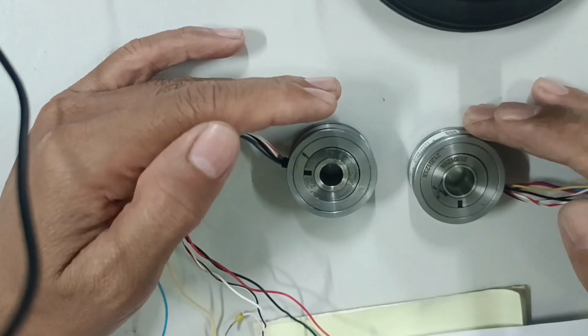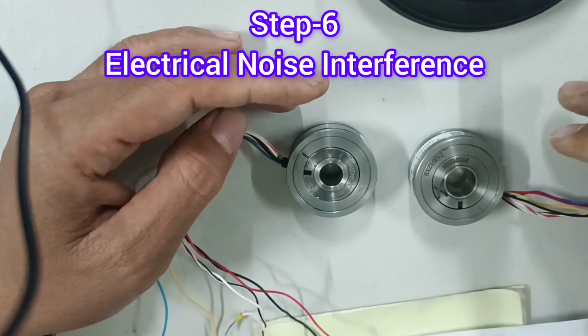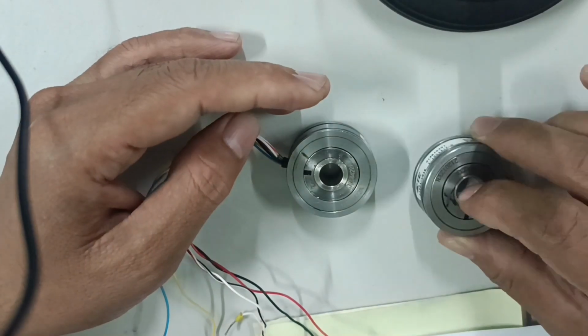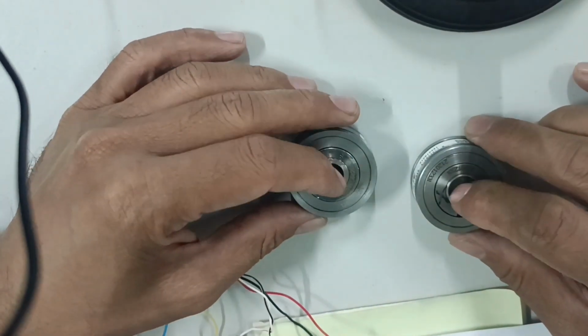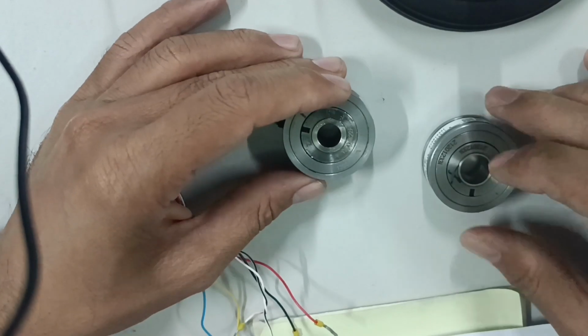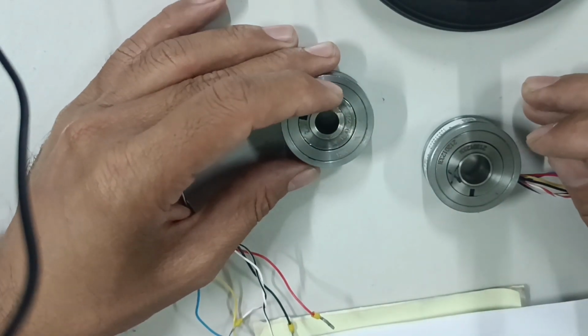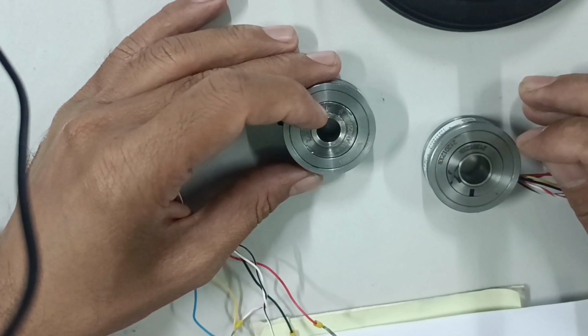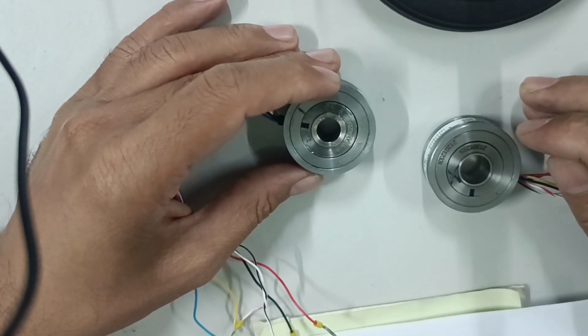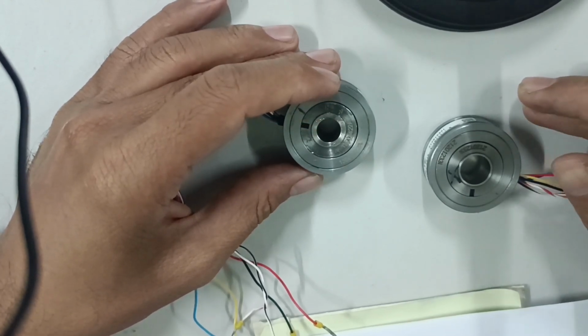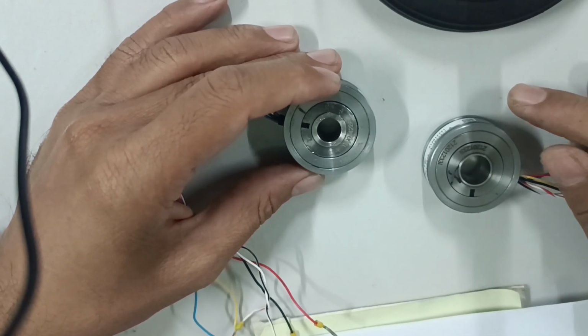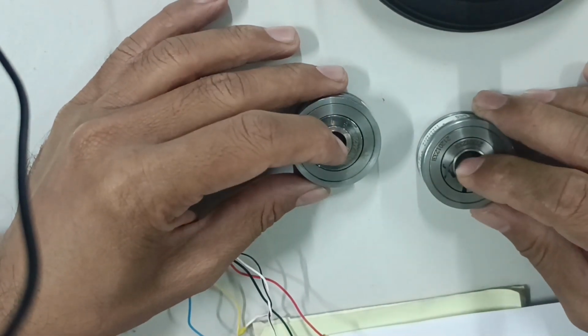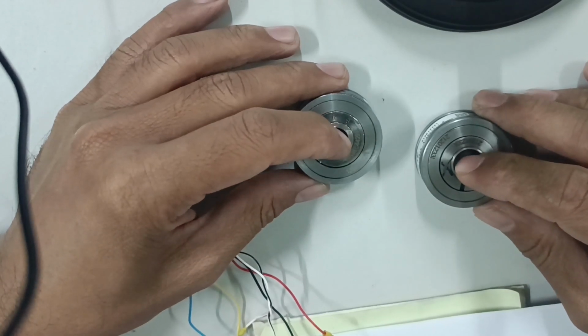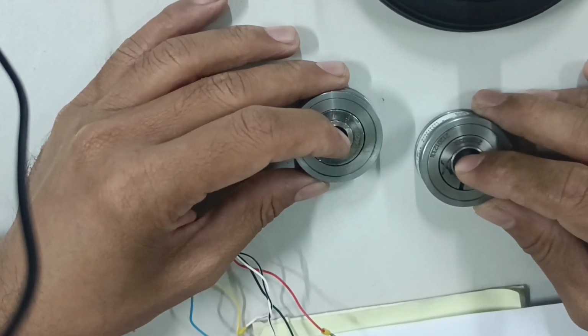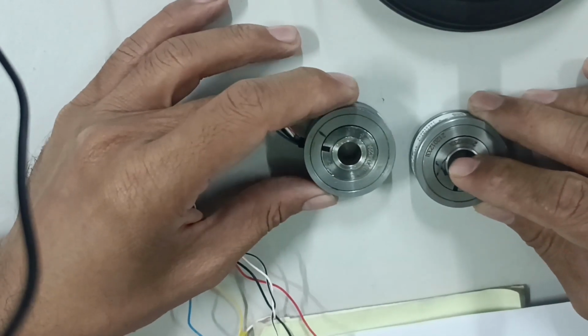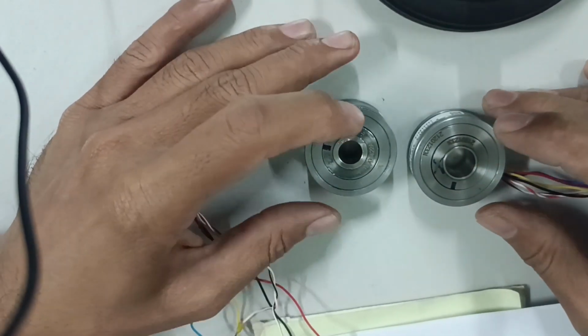And finally, step 6: check for electrical noise interference. Ensure the resolver cable is shielded and grounded properly. This is most important for the resolver and servo motor connection, including grounding properly with the body. Keep resolver cables away from high voltage lines. We have a practice in the South Asia zone where I have found that some cables are laid with low voltage and high voltage cables in the same way. That's why electrical noise interference happens in that case.